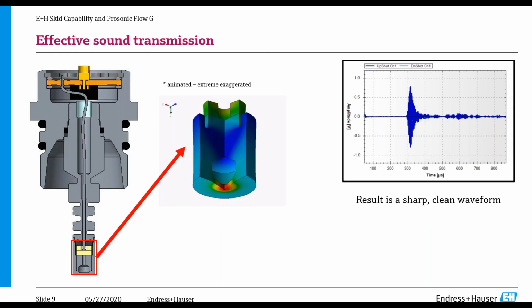So a little bit about how this is working, what we've done with the transducer design. On the left, this is the transducer that sits inside the meter body. So this is internal. This is where we're creating the ultrasonic signal itself. And you can see down here on the bottom left, the yellow part is the piezos.